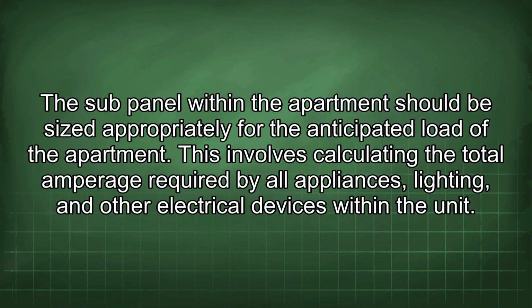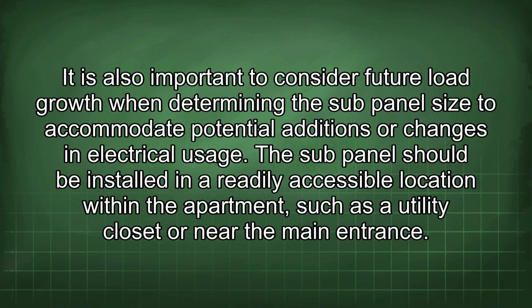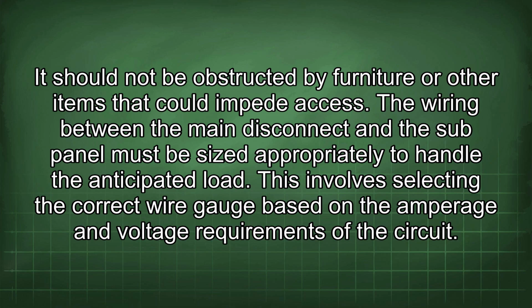The sub-panel within the apartment should be sized appropriately for the anticipated load of the apartment. This involves calculating the total amperage required by all appliances, lighting, and other electrical devices within the unit. It is also important to consider future load growth when determining the sub-panel size to accommodate potential additions or changes in electrical usage. The sub-panel should be installed in a readily accessible location within the apartment, such as a utility closet or near the main entrance. It should not be obstructed by furniture or other items that could impede access.